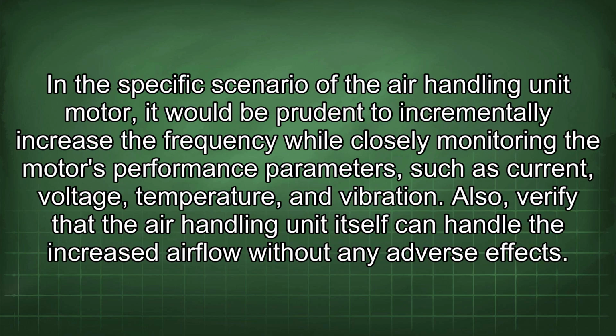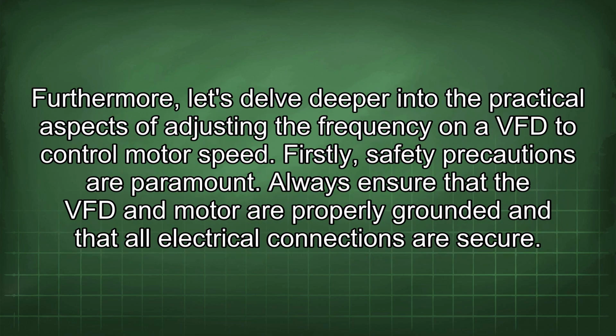In the specific scenario of the air handling unit motor, it would be prudent to incrementally increase the frequency while closely monitoring the motor's performance parameters, such as current, voltage, temperature, and vibration. Also, verify that the air handling unit itself can handle the increased airflow without any adverse effects. Furthermore, let's delve deeper into the practical aspects of adjusting the frequency on a VFD to control motor speed.